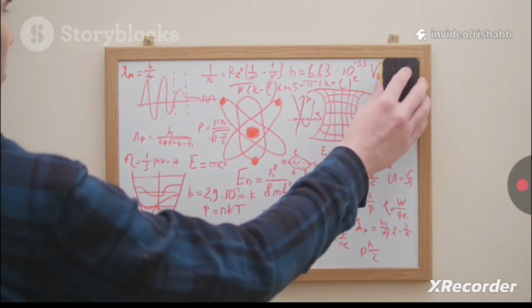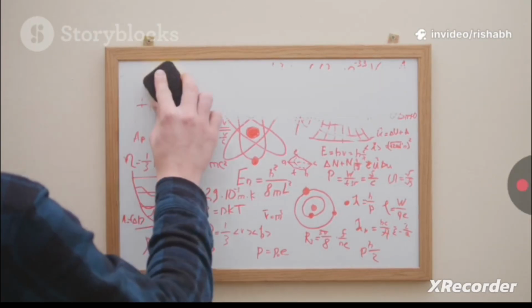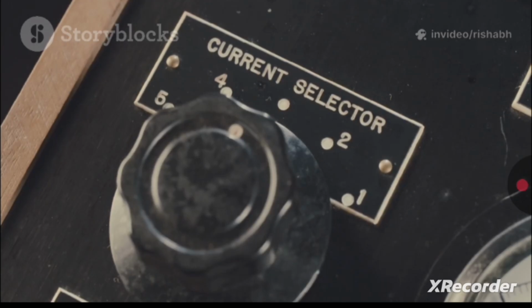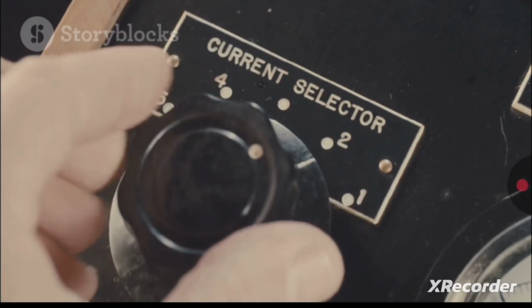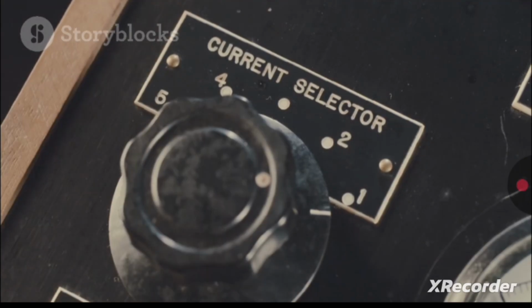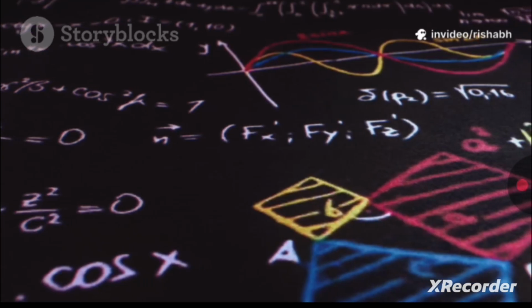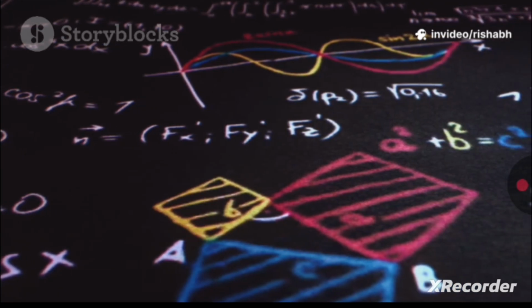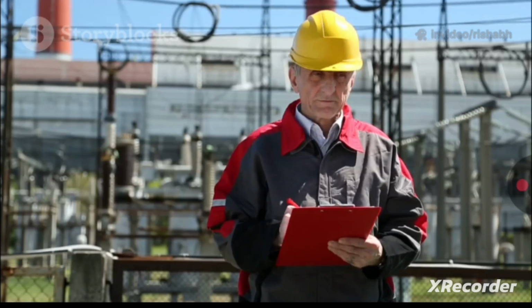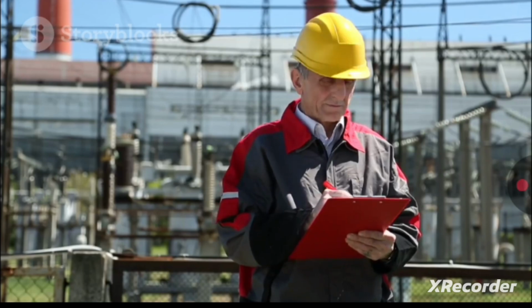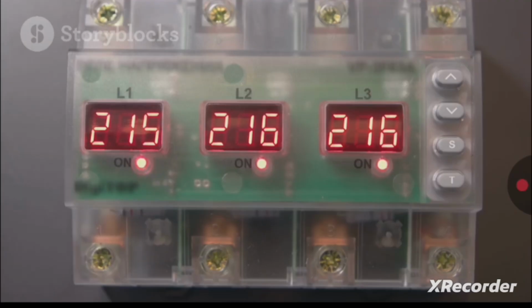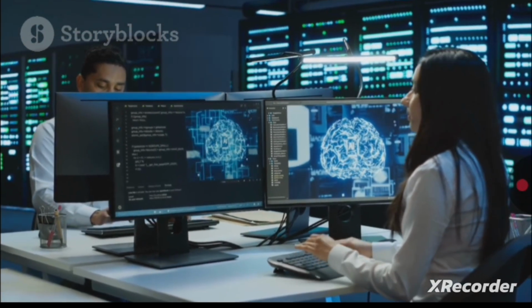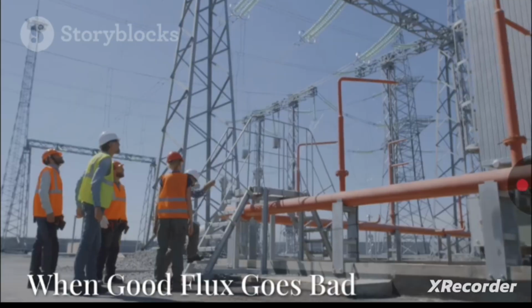The relationship that governs this whole process is simple but profound. The magnetic flux, often represented by the Greek letter phi, is directly proportional to the voltage applied to the winding and inversely proportional to the frequency of the AC power. This gives us the famous relationship: flux is proportional to voltage over frequency. This voltage over frequency ratio is the golden rule for transformer operation. As long as this ratio stays within the transformer's design limits, the magnetic flux behaves, the core does its job perfectly, and the lights stay on. It's a delicate balance that electrical engineers work very hard to maintain across the entire power grid.